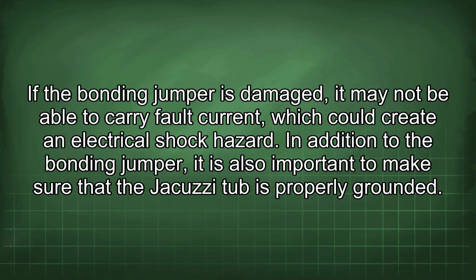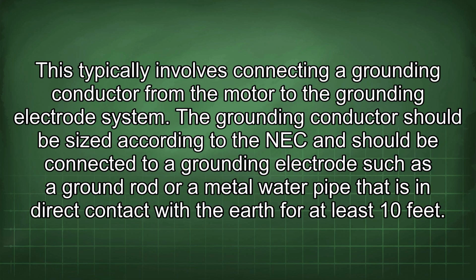properly grounded. This typically involves connecting a grounding conductor from the motor to the grounding electrode system. The grounding conductor should be sized according to the NEC and should be connected to a grounding electrode such as a ground rod or a metal water pipe that is in direct contact with the earth for at least 10 feet.